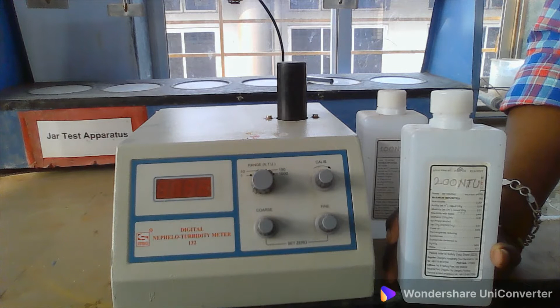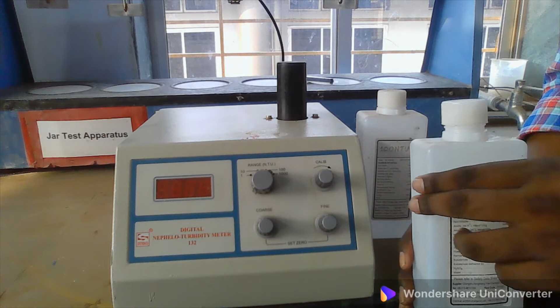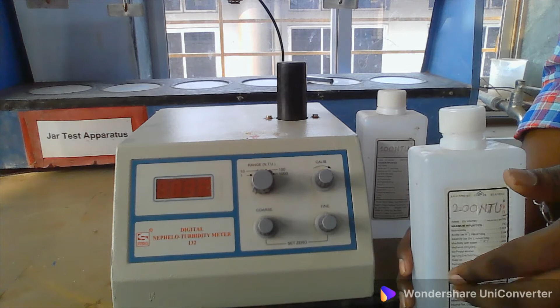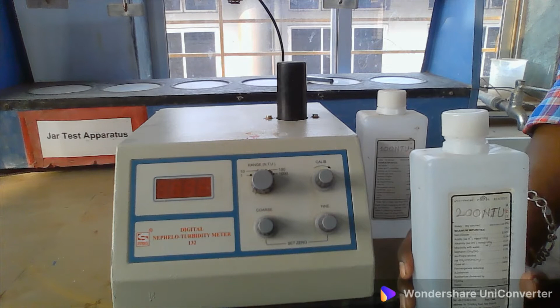But in this experiment, it is not the buffer solution. Here, formazin solution is required as a standard solution to calibrate the instrument. Formazin is a solution whose turbidity is already known. We have prepared this sample, and its turbidity is already known. We just insert it in our instrument, take the reading, and start calibration. Remember, after calibration we will start the actual sample analysis.